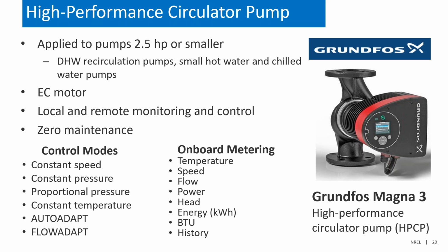The way to think through these control modes is for a typical domestic hot water recirculation application. Normally you're just going to be going with the fourth one down, the constant temperature. The pump has an internal temperature sensor within the pump. You typically set the domestic hot water return temperature set point within the pump to about 10 degrees below your domestic hot water tank set point. And so essentially the pump ramps up and down to meet that return water temperature set point.